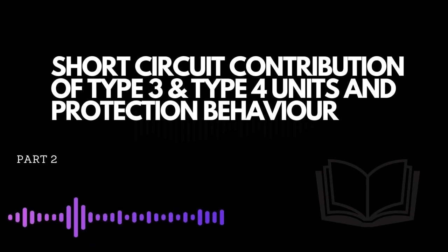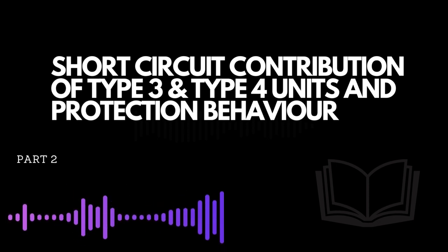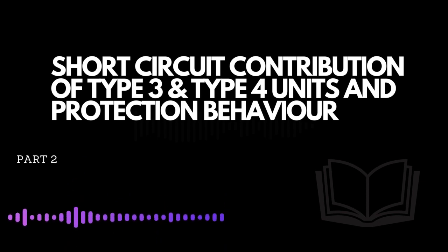Zero sequence voltage is commonly used as the polarizing quantity, although it is possible to use other magnitudes if the zero sequence voltage is not able to polarize the relay without producing deficiencies, or if there are magnetic couplings between circuits, and then -3V2 can be used instead. It is also possible to use 3I2 as polarizing quantity since it may be a more trustable magnitude.